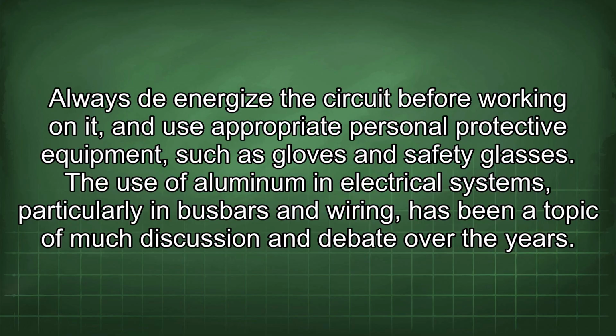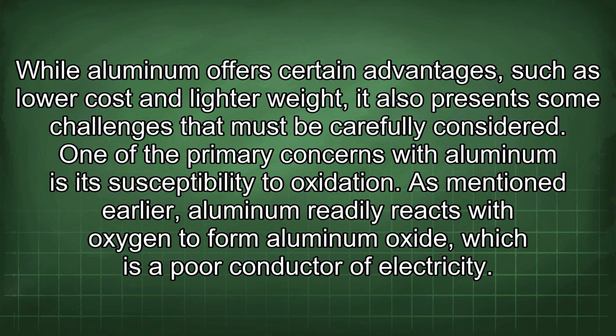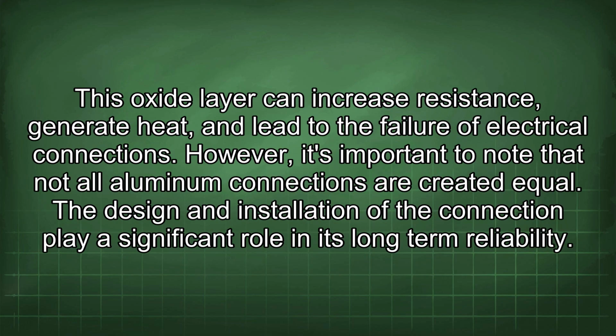safety glasses. The use of aluminum in electrical systems, particularly in busbars and wiring, has been a topic of much discussion and debate over the years. While aluminum offers certain advantages, such as lower cost and lighter weight, it also presents some challenges that must be carefully considered. One of the primary concerns with aluminum is its susceptibility to oxidation. As mentioned earlier, aluminum readily reacts with oxygen to form aluminum oxide, which is a poor conductor of electricity. This oxide layer can increase resistance, generate heat, and lead to the failure of electrical connections.